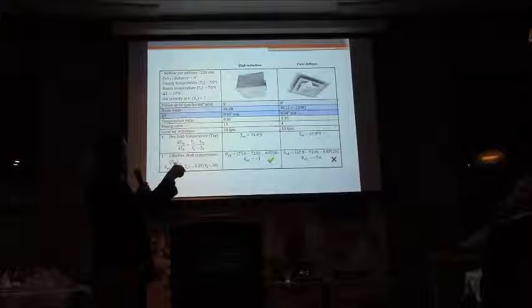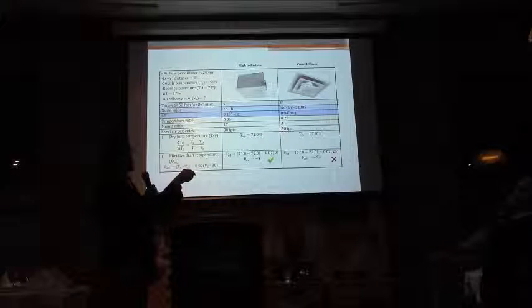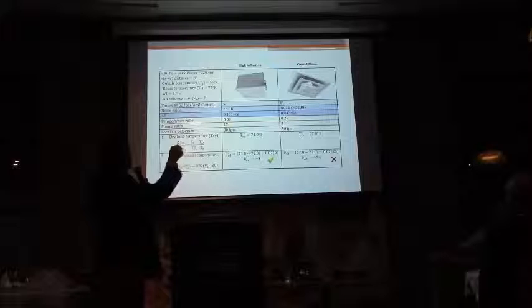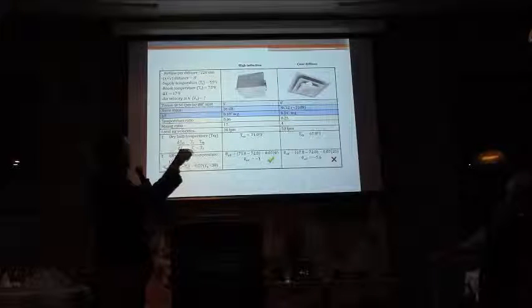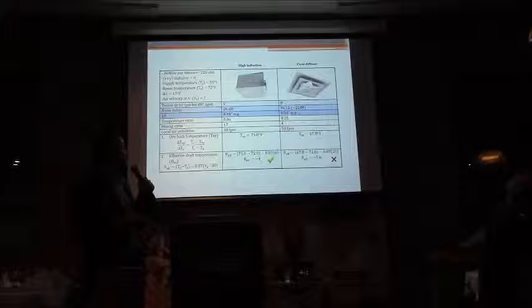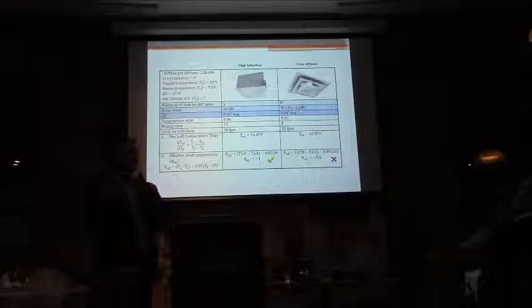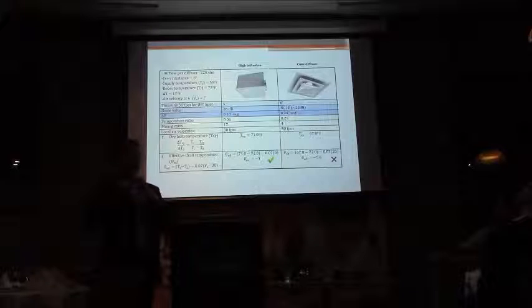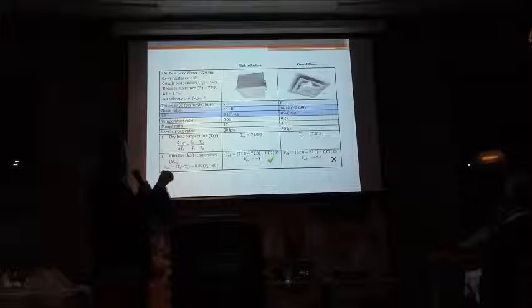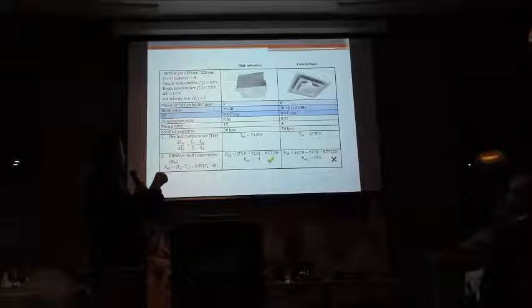So the mixing ratio is 1 divided by the temperature ratio, so we have 17 and 4. So if we have 50 feet per minute velocity of air once it reaches the occupied zone, like I said, the calculation is that it's 8 feet to X plus Y, plus the throw is 8 feet at 50 feet per minute. So we reach the occupied zone at 50 feet per minute. The other one has a throw that's actually much shorter. So we reach the occupied zone at 30 feet per minute. I was mentioning that if you're able to get that, it's a much more comfortable situation to have. And if we go with the formula of induction, we're able to find the TXY temperature.